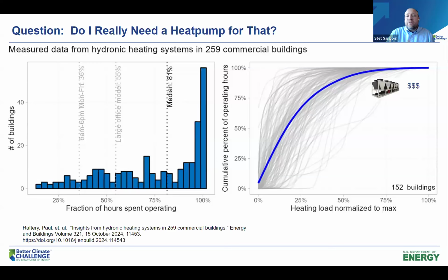So in our guide, in the scope of work and the associated guide, there are questions to ask your auditor about hybrid solutions. This is where you design a heat pump to cover maybe 75% of the hours of the year, and it may only have to be sized for about half of your load. Then let the existing boiler that's already been installed pick up those last few hours, instead of putting in a very expensive piece of equipment that's never going to run. These are questions you want to pose to your auditor to make sure you're getting the most value out of your installation, and the biggest GHG reduction per dollar spent.